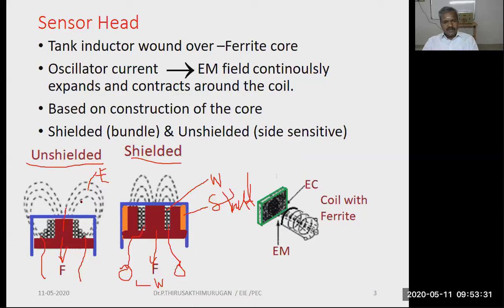So this is magnetic. What is the major difference between these two? We can classify based on the construction of the core. So here you see the magnetic field generated by the unshielded sensor head. It is like this. That means this can sense an object at the side also. That is, side sensitivity is available with the unshielded. Whereas shielded is only for the front. It will sense only the directional objects, the objects opposed to the field. The major advantage of unshielded is that the range can be large. Mostly this unshielded type of sensor head is used in industry. So these two terminals we can connect to the next stage. This is the sensor head stage.